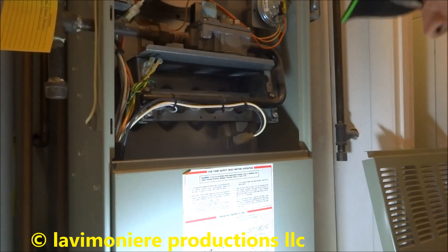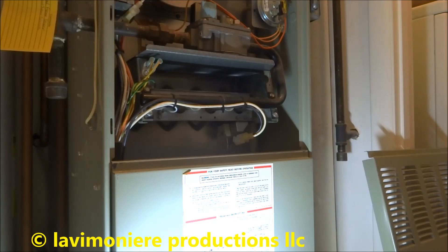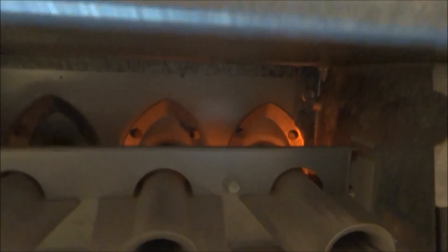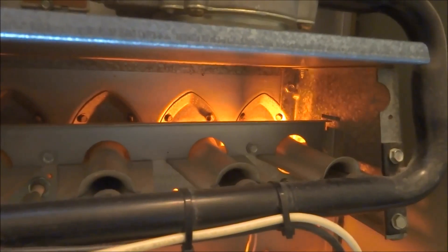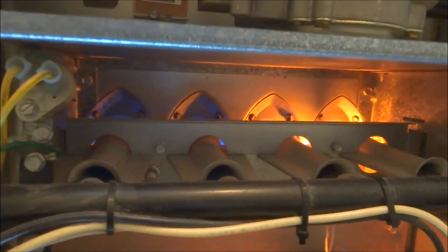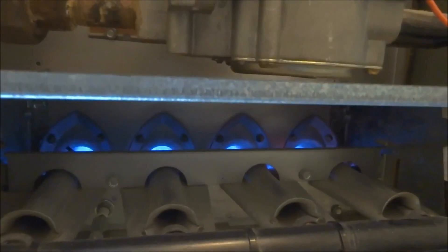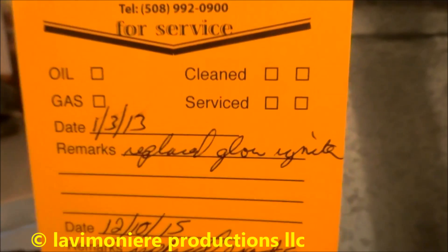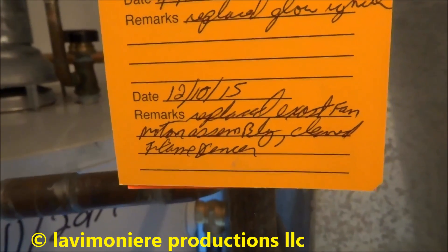Alright, why don't you go turn it up and we'll see what happens here. I think that's what it is. I was here — I think I replaced the igniter back in 2013. Last year I cleaned the flame sensor. Yeah, she fired up! Houston, we have ignition. I replaced it three years ago, it looks like. Last year we replaced the exhaust fan motor.